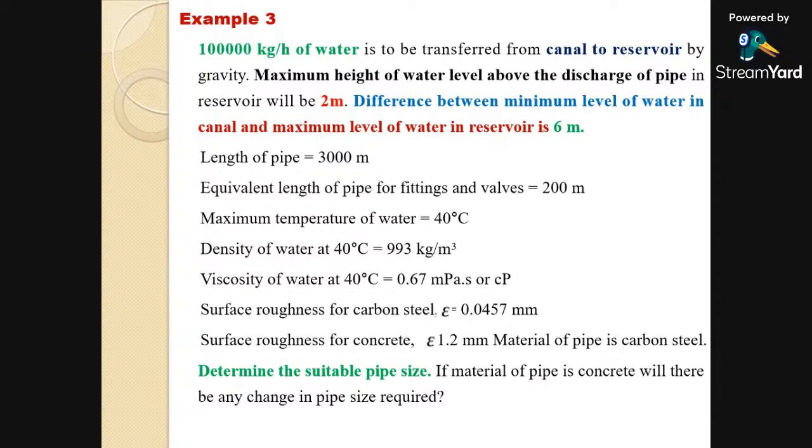म्हणजे जर फिटिंग मध्ये जेवढा प्रेशर ड्रॉप मिळतो, समजा 1 किलो पास्कल जर फिटिंग मध्ये 10 फिटिंग आहेत आपल्याकडे आणि 10 फिटिंग मध्ये जर 1 किलो पास्कल प्रेशर ड्रॉप मिळत असेल, तर स्ट्रेट पाईपची लेंथ किती असेल 1 किलो पास्कल प्रेशर ड्रॉप मिळाला, that is equivalent length, and it is always expressed in terms of straight pipe. म्हणजे अगोदर काय होता, आपला जो स्ट्रेट पाईप होता, स्ट्रेट पाईप मध्ये आपण काय केलंय, फिटिंग्स लावल्या. फिटिंग लावल्यामुळे काय होईल, लॉसेस वाढेल. आता अगोदर प्रेशर ड्रॉप 0.5 किलो पास्कल होता, फिटिंग लावल्यामुळे तो 1 किलो पास्कल झाला. तर 1 kPa प्रेशर ड्रॉप मिळवण्यासाठी स्ट्रेट पाईपची लेंथ किती लागेल? आणि हे ऑब्वियस आहे की स्ट्रेट पाईपची लेंथ जास्त लागेल, कारण फिटिंगमध्ये जास्त लॉसेस आहे, म्हणजे कमी लेंथमध्ये जास्त लॉसेस मिळतील. आणि जर फिटिंग काढली तर लेंथ तुमची इन्क्रीज होईल, जर सेम प्रेशर ड्रॉप मिळवायचा असेल, आणि ती लेंथ म्हणजे इक्विव्हॅलंट लेंथ आहे. Is it clear?